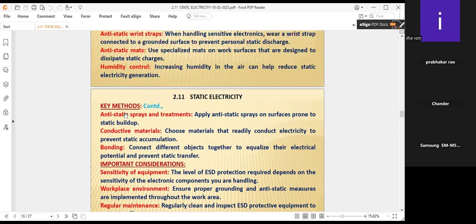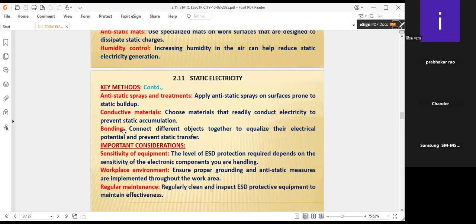Bonding is also important, apart from earthing or grounding. Bonding connects different objects together to equalize their electric potential and prevent static transfer, such as when transferring flammable liquid or oil from one place to another. As mentioned earlier, there is a transfer of electrons, and sparks may occur due to an imbalance of electrons, causing charge leaks. To bring that imbalance back to balance, you connect the bonding to the flammable liquid, which neutralizes the release of electrons. This will be explained further in the coming slides.